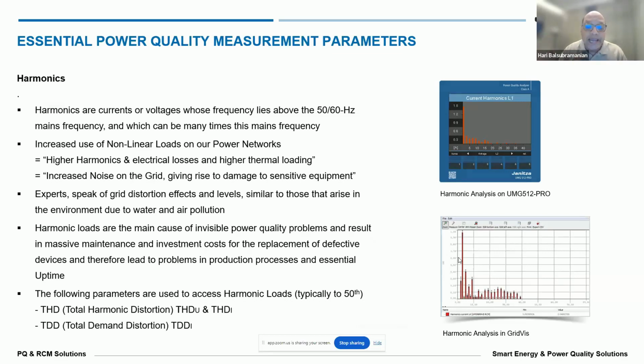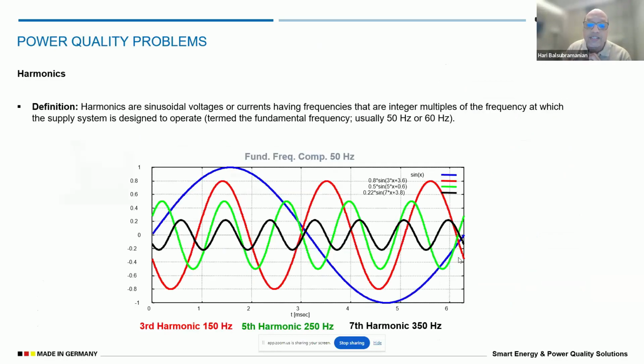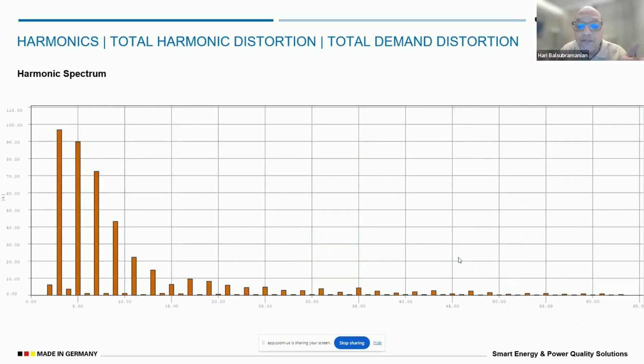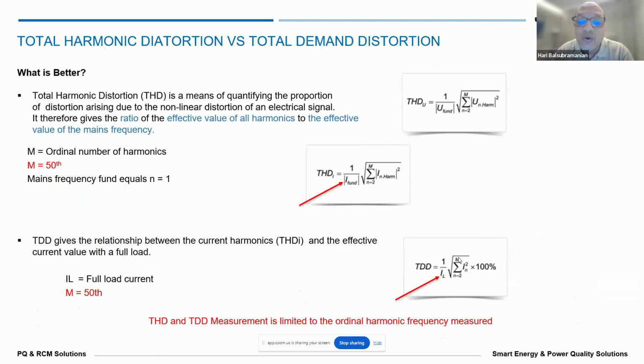So you have a spectrum of harmonic frequencies, from the 1st to the 63rd or the 1st to the 30th. Based on these frequencies and the harmonic content, we calculate the total harmonic distortion. In this formula, M is the ordinal frequency we measure, which depends on the Fourier transform and how we use it. We take the sum up to the order M. M can be the 50th harmonic, the 63rd harmonic, the 30th or the 15th, depending on the measurement device.